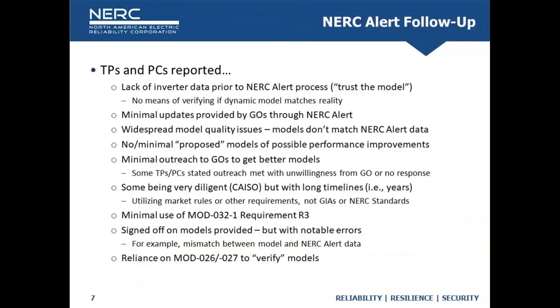And there's this trust-the-model concept where I receive a model from a generator owner and I'm expecting that that model is 100% accurate, or as accurate as reasonably expected. And there's no means of verifying that data. When you look at, say, the pro forma LGIA for a synchronous generating resource, you are required to provide capability curves, D curves, protection settings, spec sheets, all of this stuff, and none of that is required for inverter-based resources.